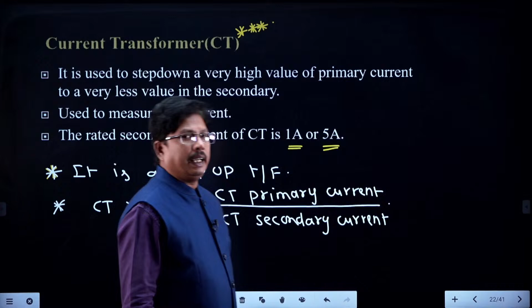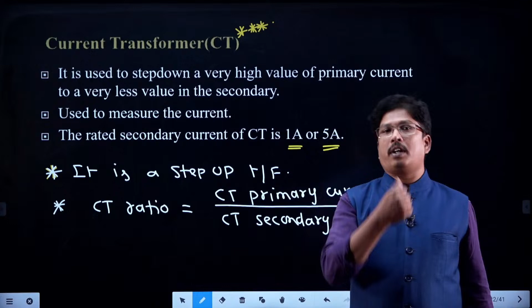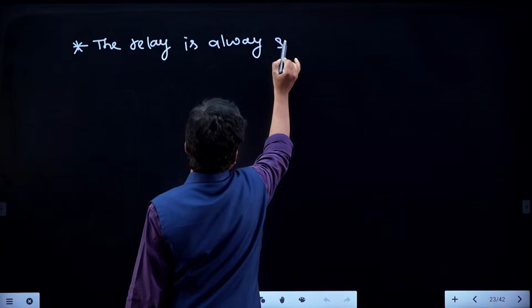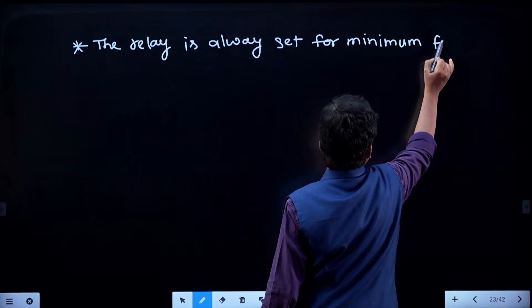There are two types of CTs: one for measuring purpose, one for protecting purpose. The CT which we use for protecting purpose works with the relay. Whenever you are using the CT with the relay, that relay is always set for minimum fault current, as it has to sense all types of faults. LG fault, LL, triple LG, it has to sense all types of faults, that is why it is set for minimum fault current.